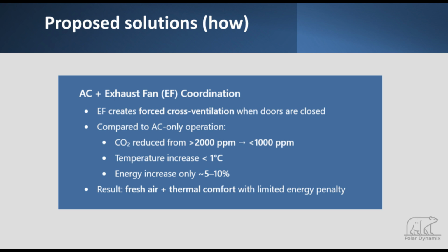The increase in room temperature is less than 1 degree Celsius, and the additional energy use is limited to only about 5 to 10%. As a result, the room receives fresh air and maintains thermal comfort at the same time, with only a small energy penalty.